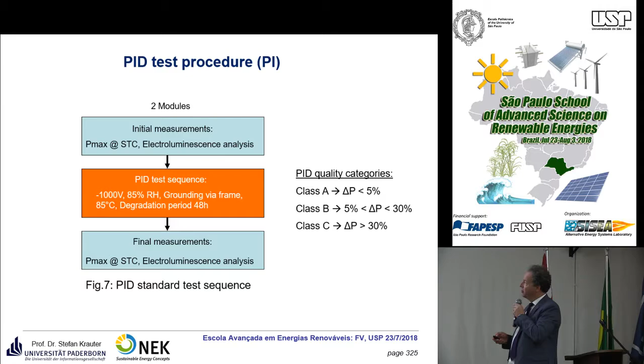You see the grounding of the negative pole also helps, so we just avoid the negative polarity here. If it's not possible - if you don't have a transformer, if you're using a transformer-less inverter, which becomes more fashionable at the moment and much cheaper - then this is not suitable to ground it.